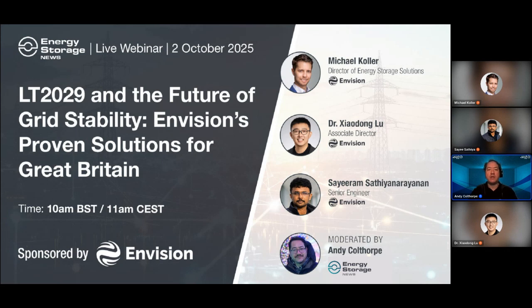Today's webinar focuses on a topic that the global industry is gradually beginning to recognise: the need for low-carbon sources to provide system stability services that have been traditionally played by thermal generation assets. As the term strongly implies, these services, which include inertia and short-circuit ratio, are necessary for the stable functioning of the electricity grid.